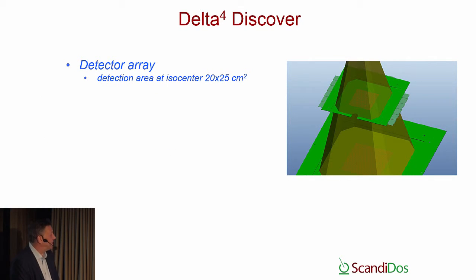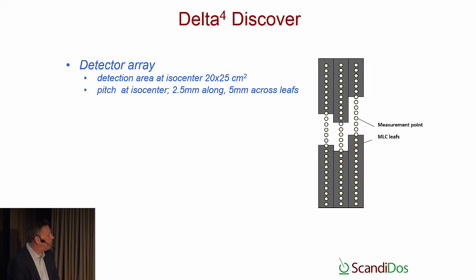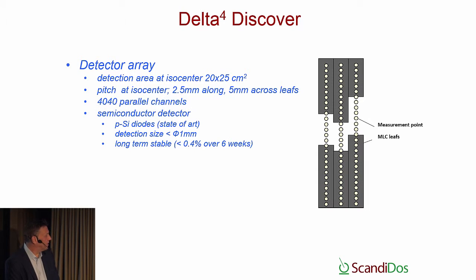The array itself is 20 by 25 cm, projected to isocenter. Pitch at isocenter is 2.5 millimeter along and 5 millimeter across the leaves, and this is for a 5 millimeter leaf collimator. Thereby it has 4040 parallel channels, and it's a semiconductor detector that is used. It's a P-type silicon detector, which is completely outstanding on the market in performance. The detector size is small. It's exactly 1 millimeter diameter, and the stability is very, very good.